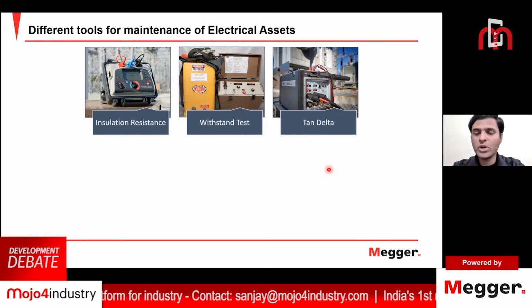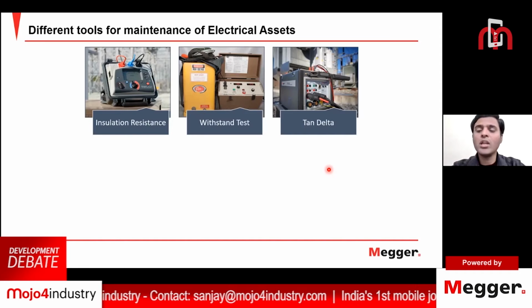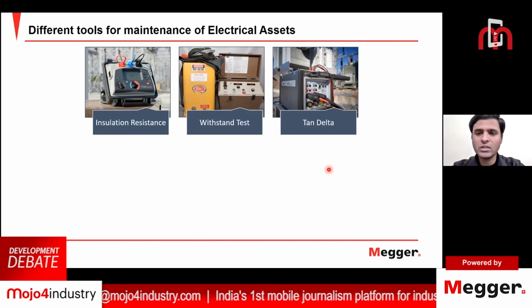However, it will not help you understand whether that particular asset is deteriorating in the online condition. Tan delta measurement is one of the offline preventive maintenance tests.